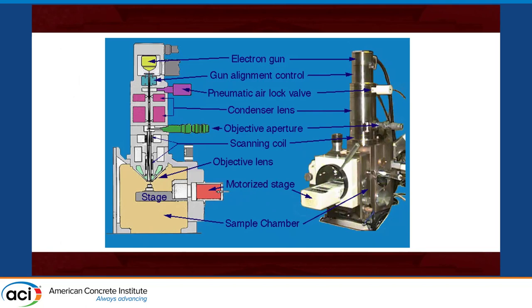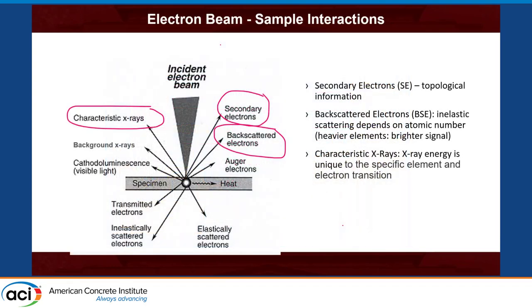This is the main difference between the optical microscope and scanning electron microscope. You see the motorized stage — you just put the sample down and place it there. But a very high vacuum is necessary for observation. The sample undergoes a tremendous amount of vacuum, and sometimes there are some artifacts. You need to identify situations where artifacts occur due to the conditions the specimen undergoes.